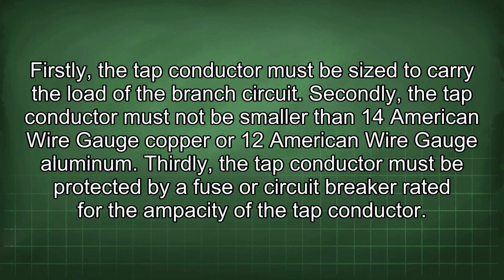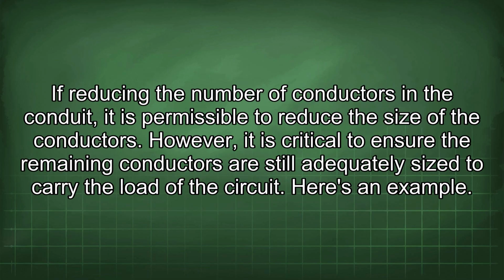Firstly, the tap conductor must be sized to carry the load of the branch circuit. Secondly, the tap conductor must not be smaller than 14 American wire gauge copper or 12 American wire gauge aluminum. Thirdly, the tap conductor must be protected by a fuse or circuit breaker rated for the ampacity of the tap conductor. If reducing the number of conductors in the conduit, it is permissible to reduce the size of the conductors. However, it is critical to ensure the remaining conductors are still adequately sized to carry the load of the circuit.